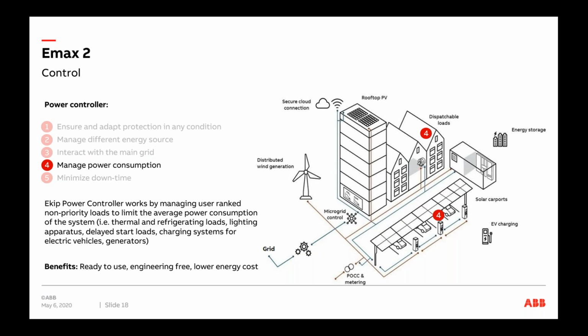Power consumption, we're talking about something we call the power controller. So a power controller is an accessory, which is now a software accessory, which means the hardware remains the same and the breaker can be upgraded to have that functionality. Now, the power controller basically is what controls loads downstream. So the Emax 2 as a main breaker or main master behaves as the brain for the whole power distribution setup with, let's say, up to 15 devices downstream.